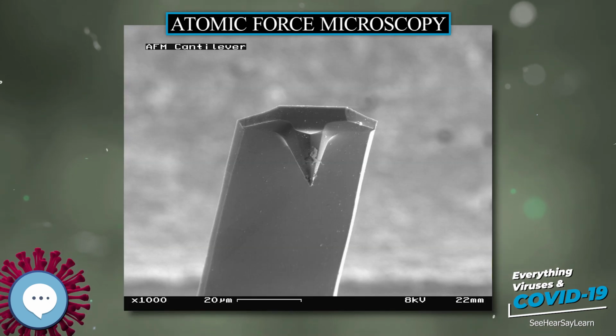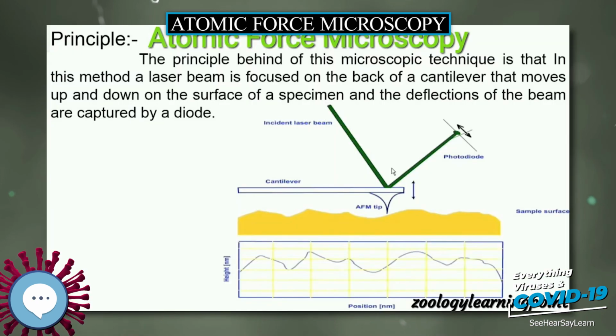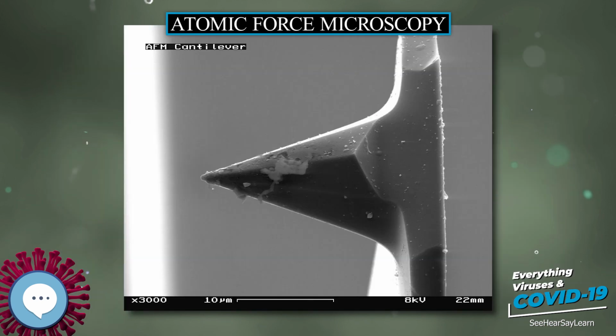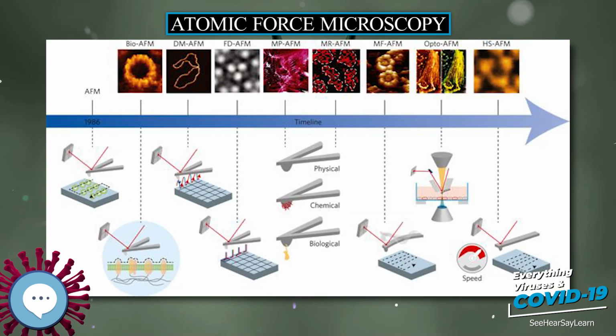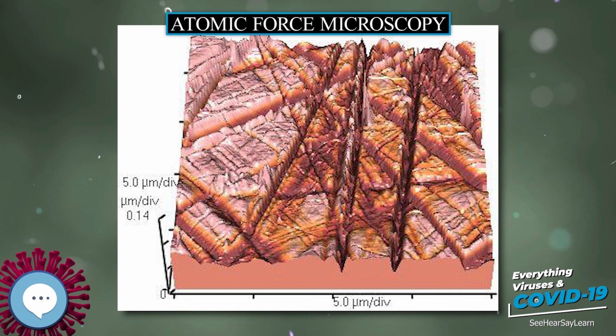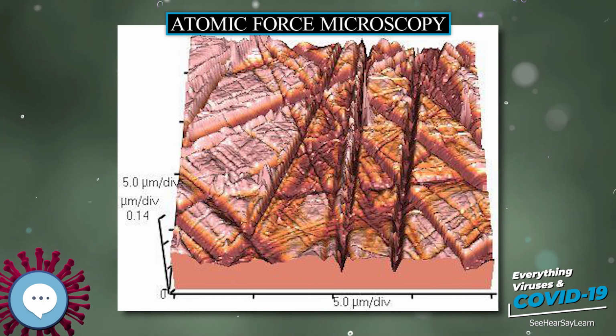Due to the nature of AFM probes, they cannot normally measure steep walls or overhangs. Specially made cantilevers and AFMs can be used to modulate the probe sideways as well as up and down, as with dynamic contact and non-contact modes, to measure sidewalls, at the cost of more expensive cantilevers, lower lateral resolution and additional artifacts. Other applications in various fields of study.